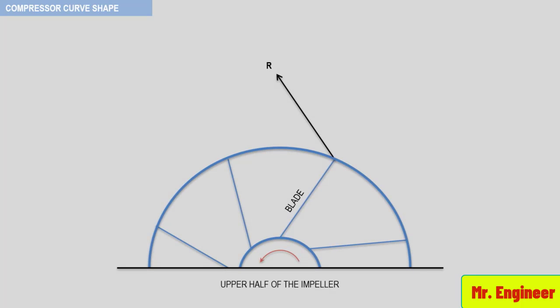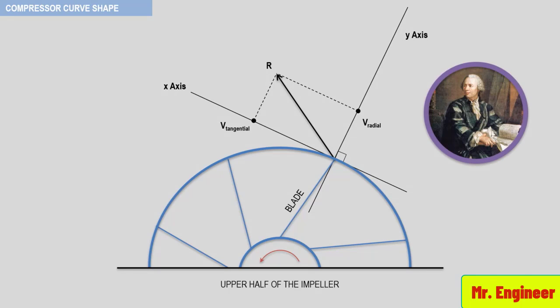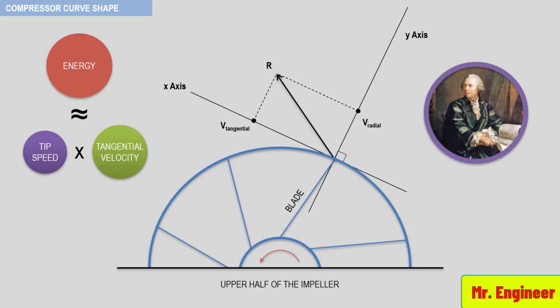If we now resolve the absolute velocity into X and Y components, the X-axis projection of the component is the tangential velocity of the gas at the impeller discharge. According to the energy equation of Euler, the energy created by any dynamic machine is proportional to the product of the tip speed and the tangential velocity.